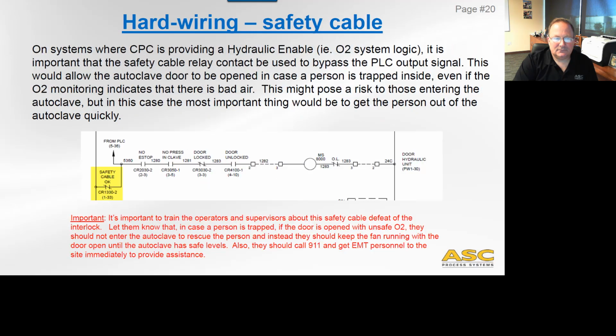Let's see here. Now, the special consideration of the safety cable is if you have a safety cable on an autoclave which has a hydraulic door, okay. Normally, we would have an interlock with the hydraulics that would disallow it from operating when the oxygen monitoring system determines there's unsafe air in the autoclave. But there's a caveat to that.